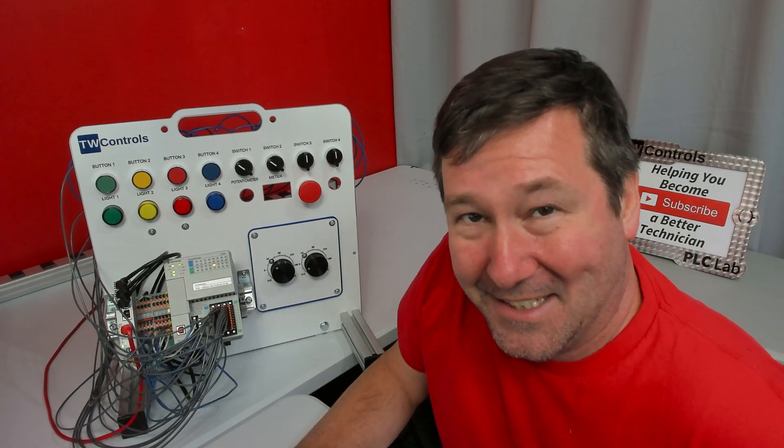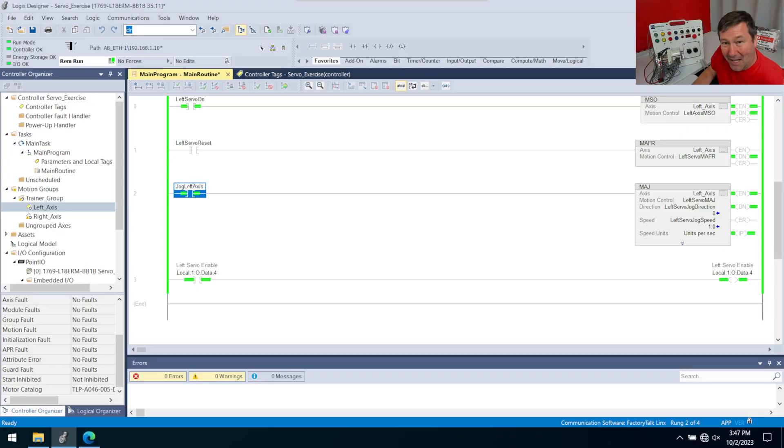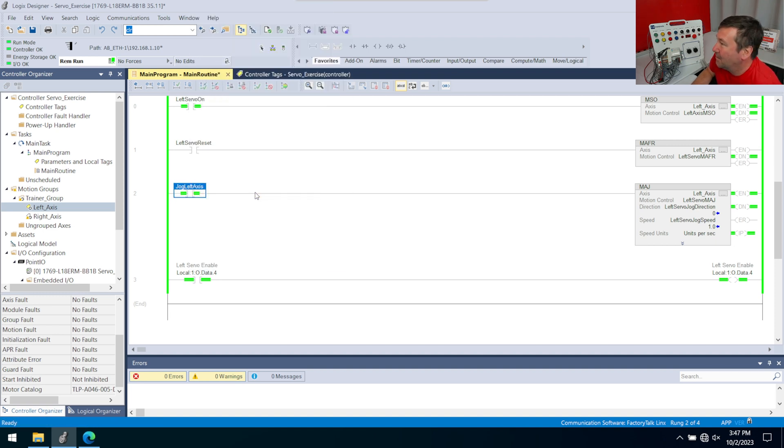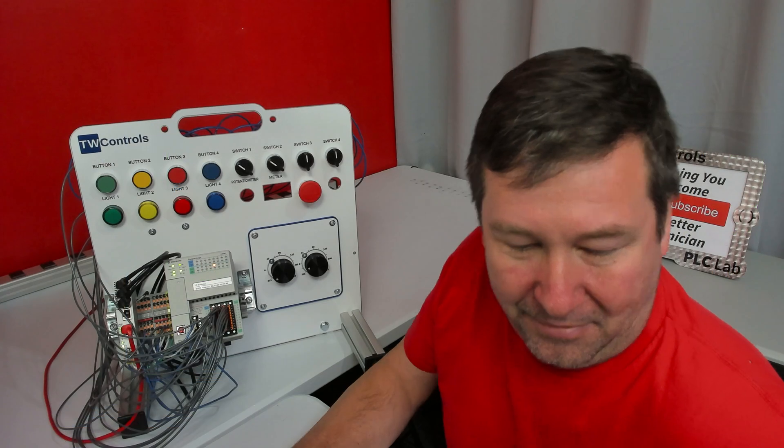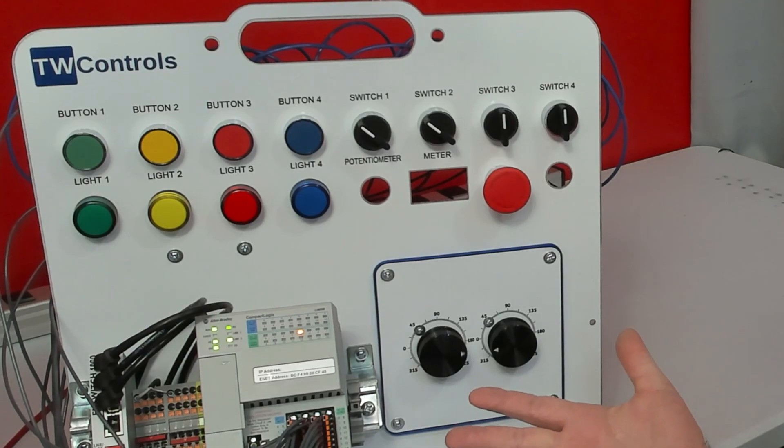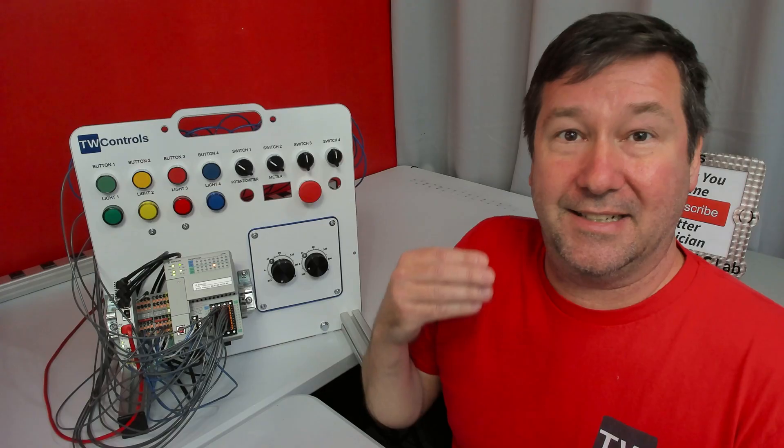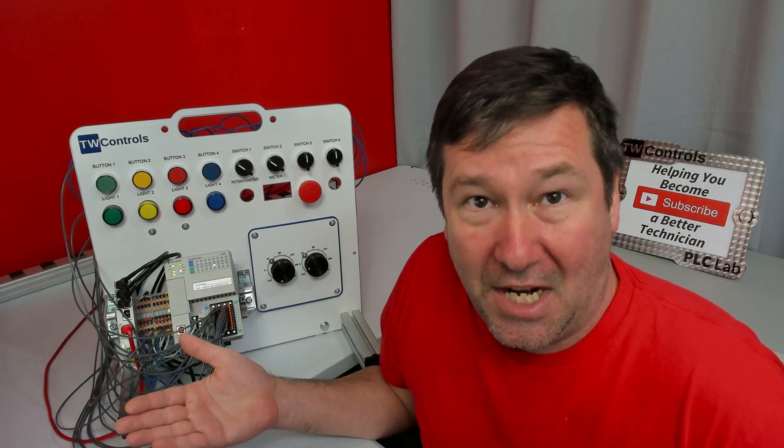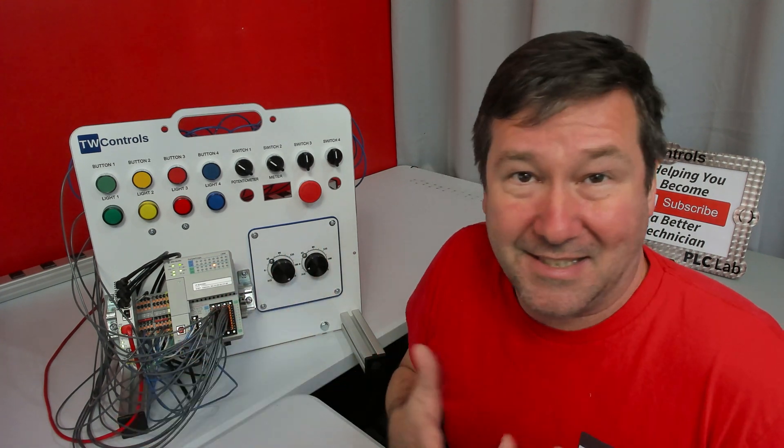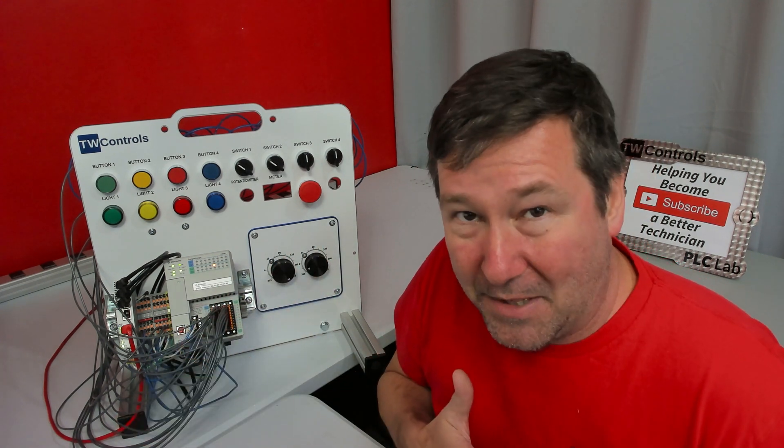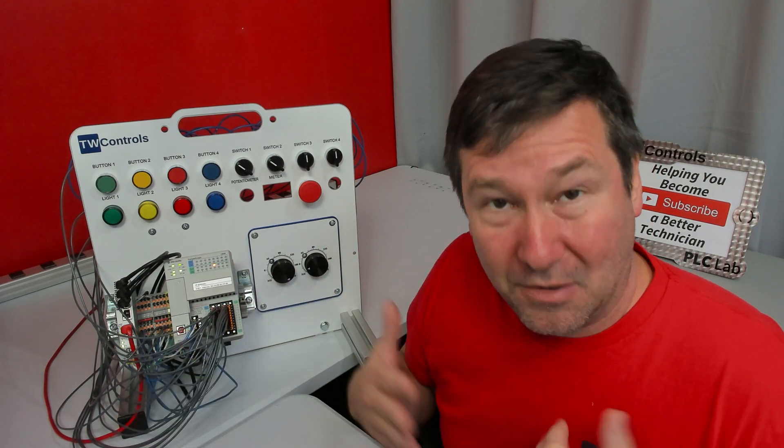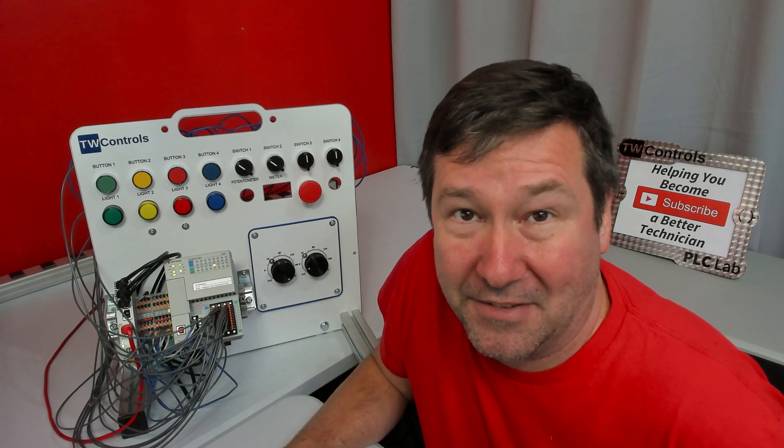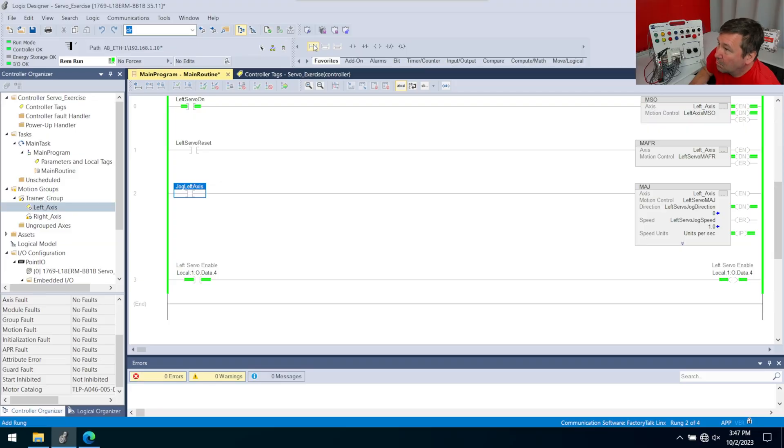Now, here's the next stumbling block. Most people now think that we're going to right click jog left axis and we're going to toggle the bit again. That should have turned it off, but yeah, we're still rotating. Because it is a command to start jogging. It doesn't say anything about stopping when it's false. So we will need to issue a stop command.